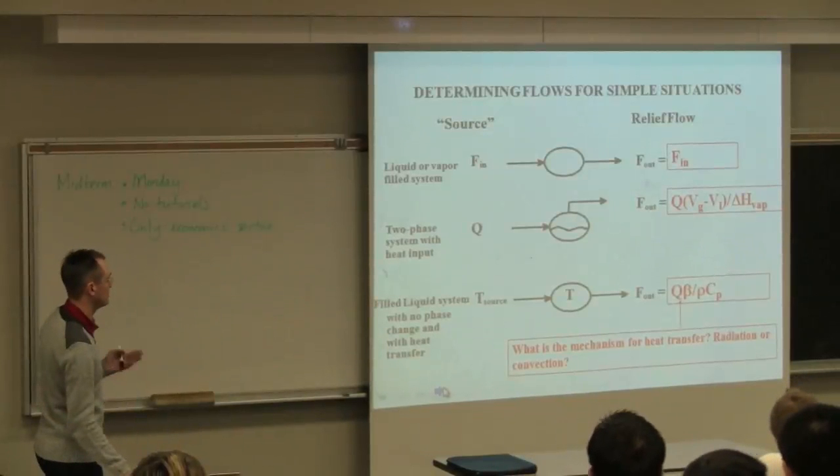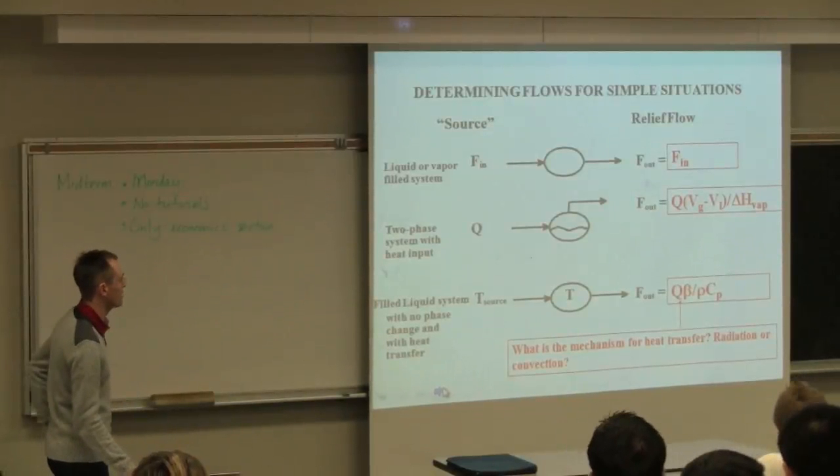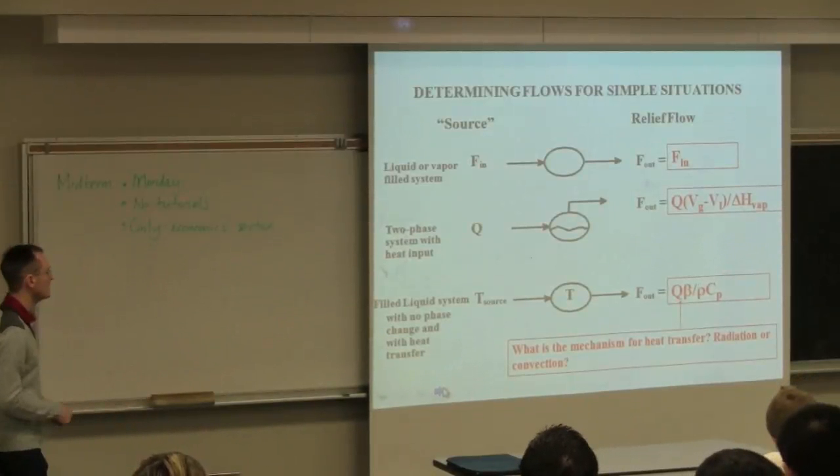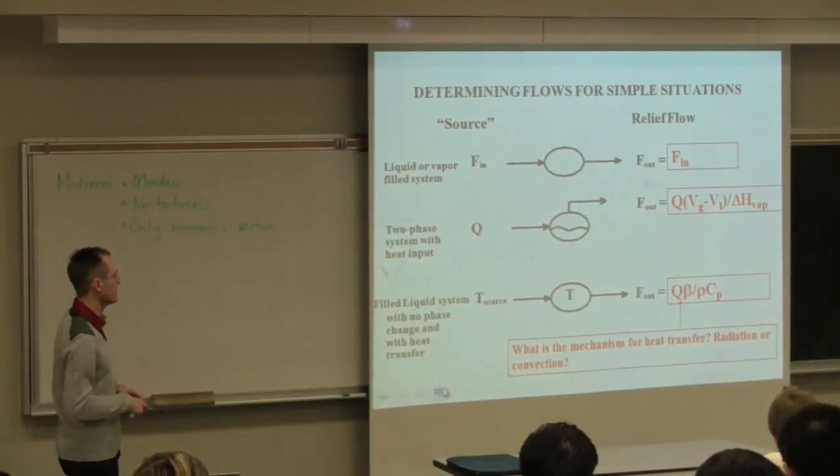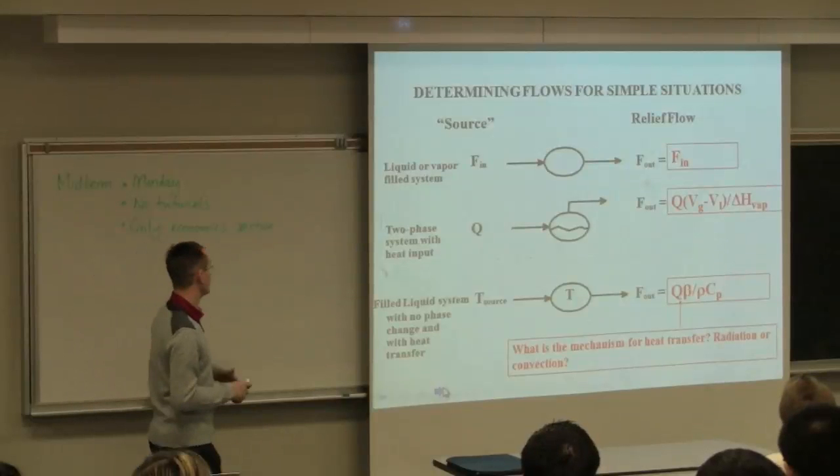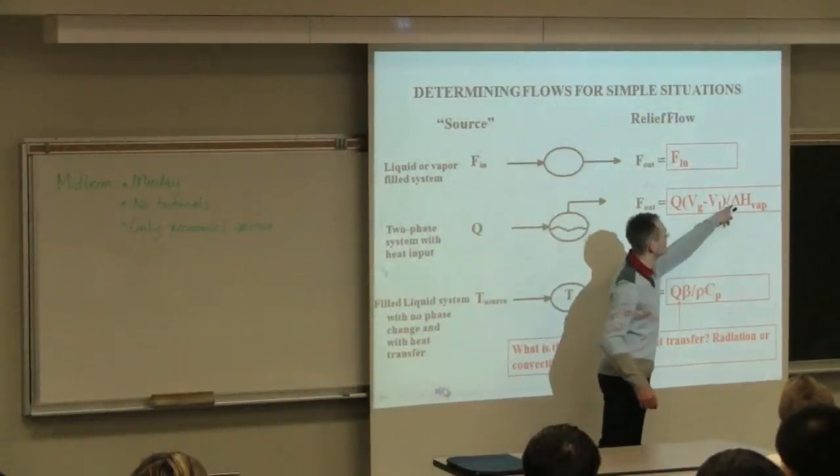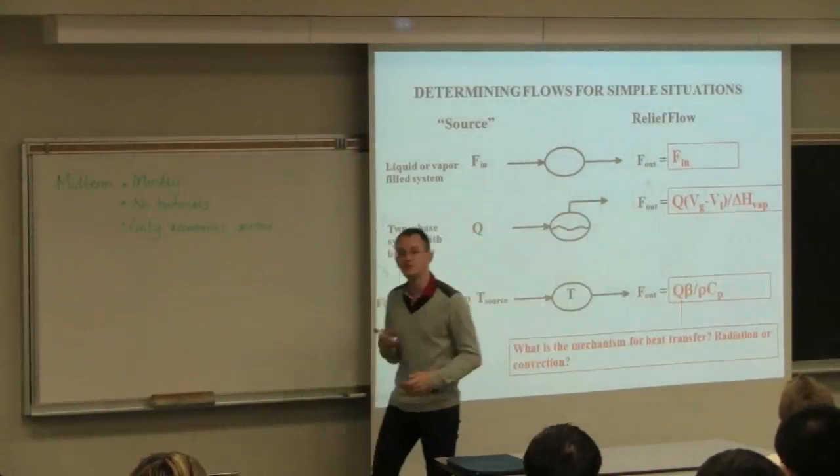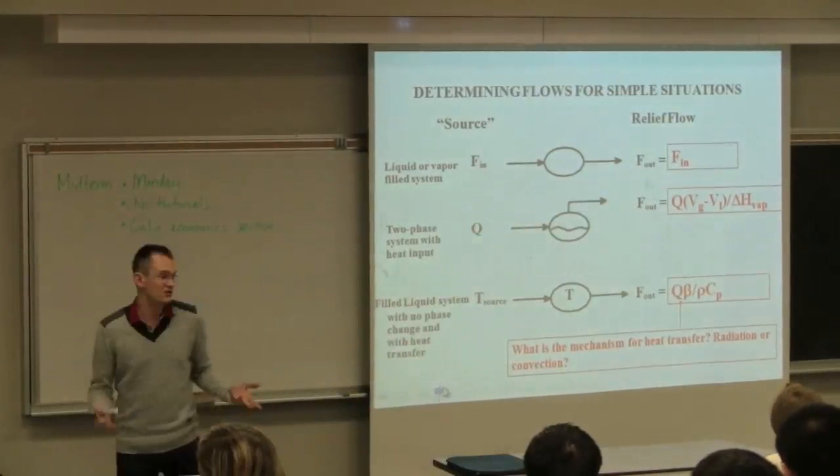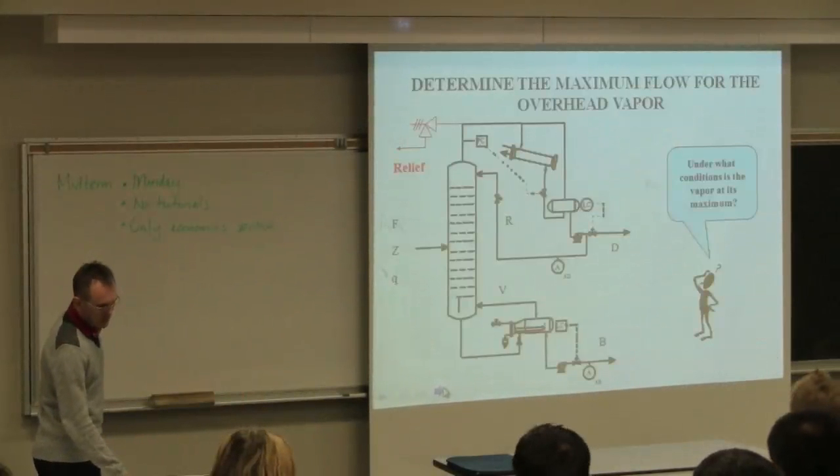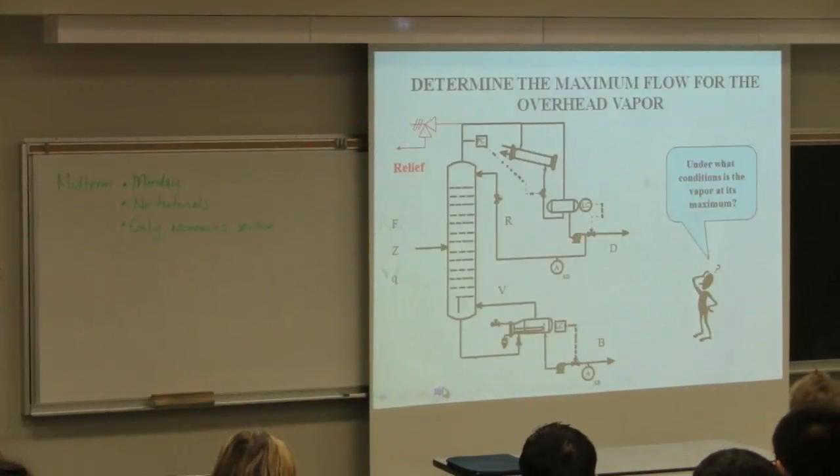For systems that happen to be two phases, so here we've got liquid and a gas phase above it and there's heat input, for example from a fire or heat around it, and when that heat input gets too high, we need to apply relief. The expected flow out is a function of the heat of vaporization, how much heat is being consumed by boiling liquid to gas.